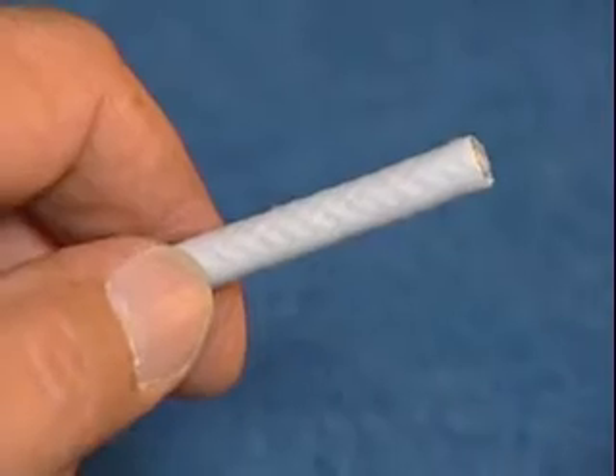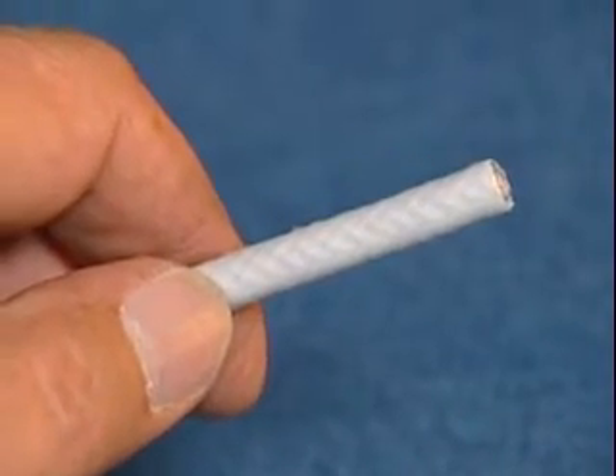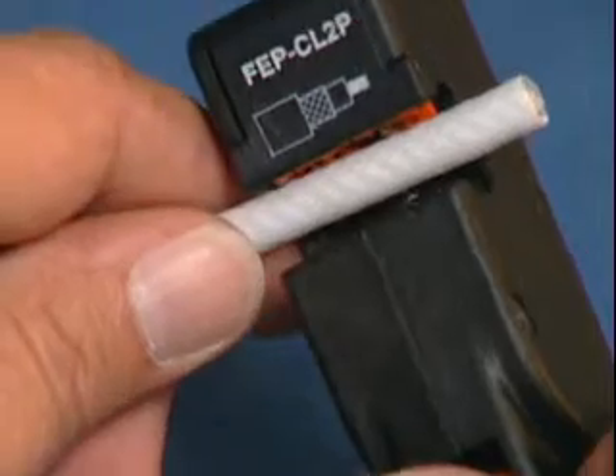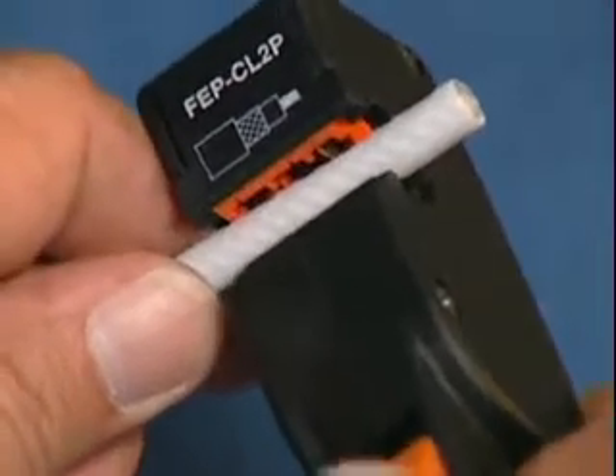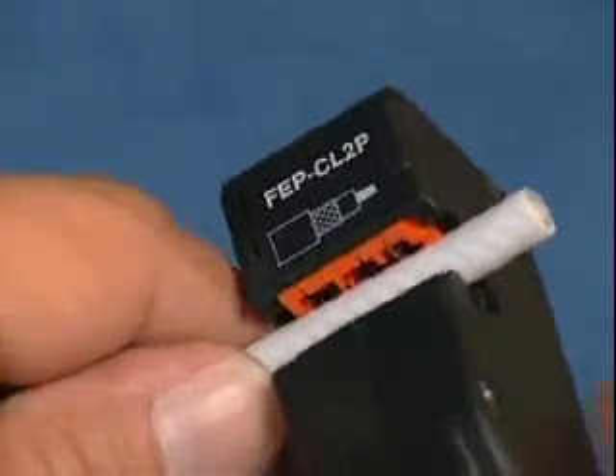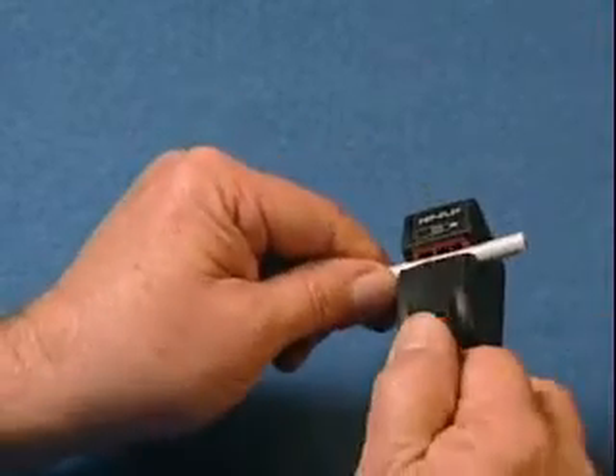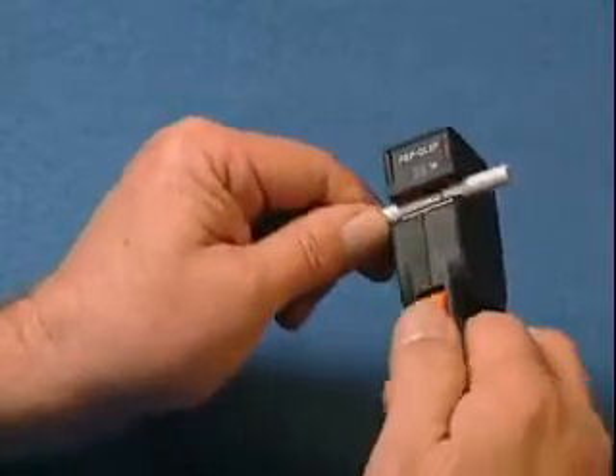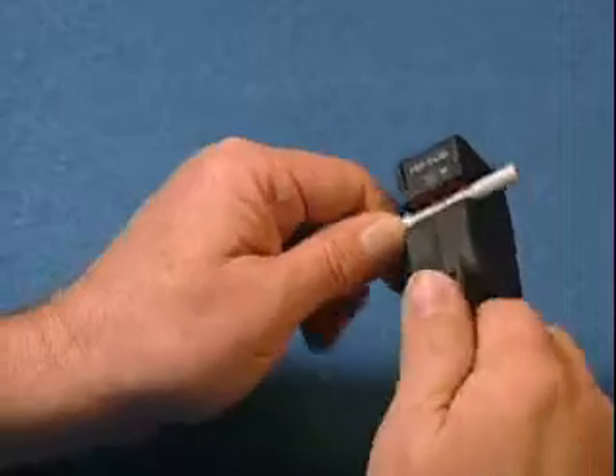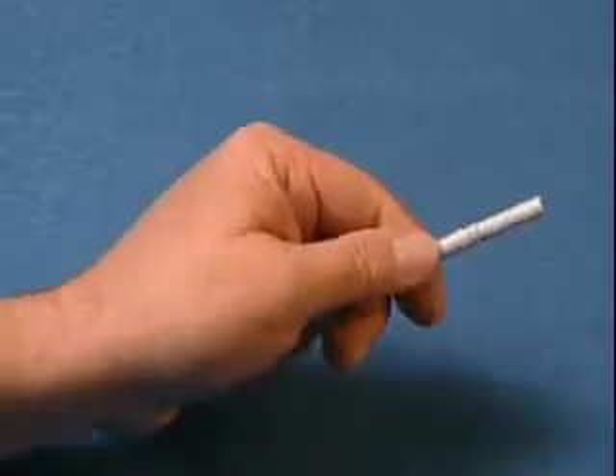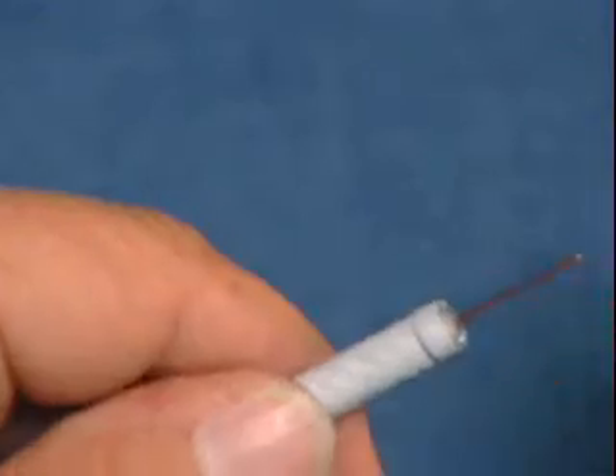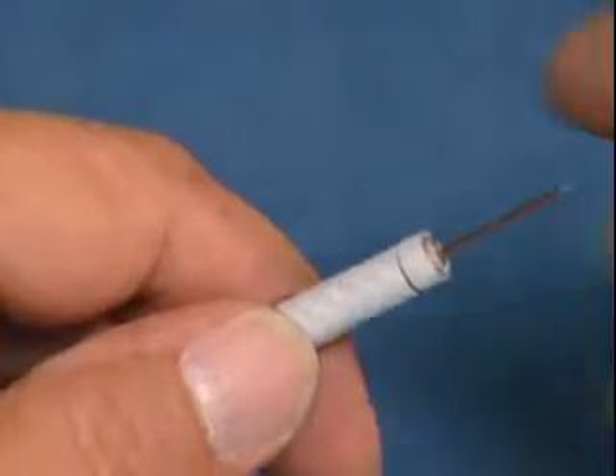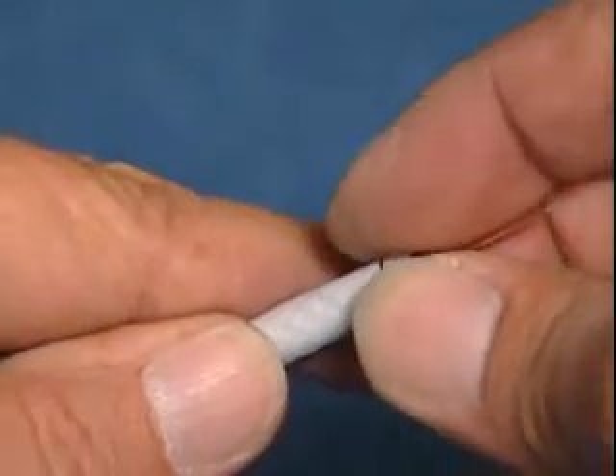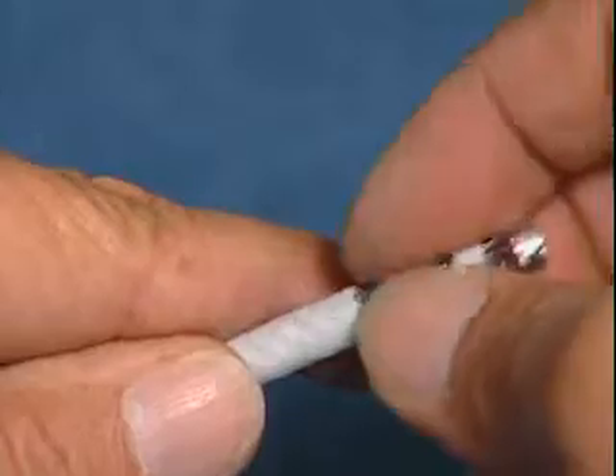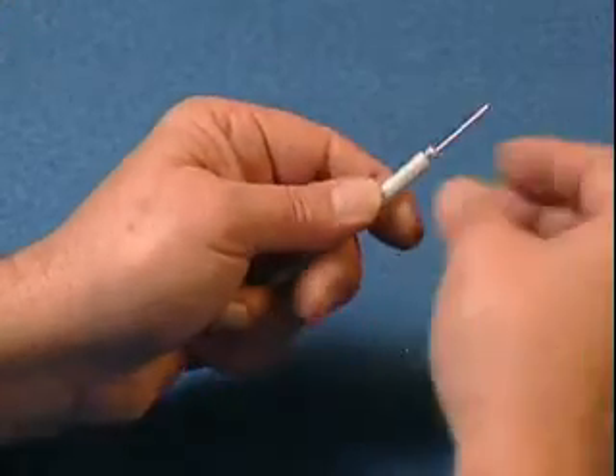Once we have calibrated our coaxial cable stripping tool, we are ready to connectorize plenum control net cable. Be sure the cable is straight and extends through the stripping tool by at least 1 inch. Remember to rotate the stripping tool at least twice for each click of the chamfer ring. Remove the jacket, braid, and dielectric from the center conductor using a twisting turning motion. Remove the jacket and braid from the second cut, leaving the bonded foil.